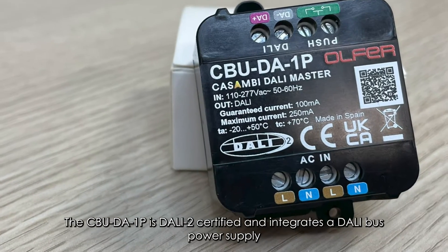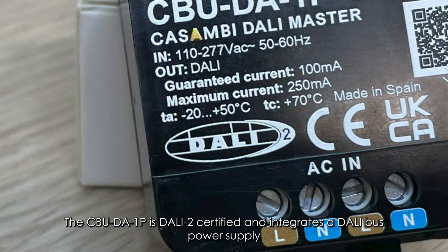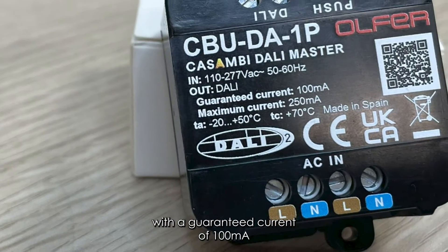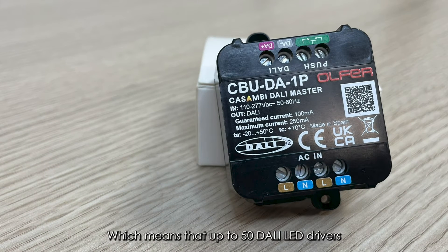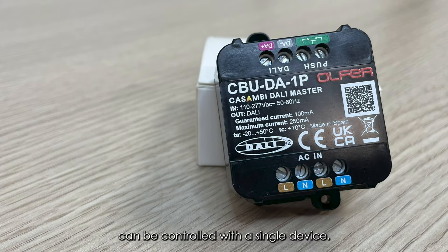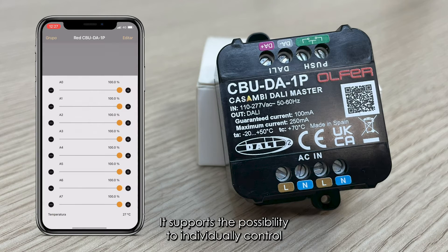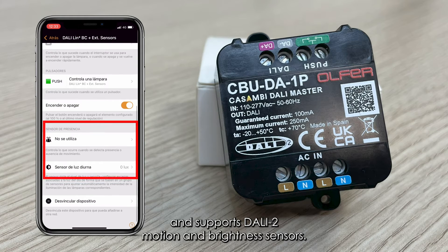The CBU-DA-1P is DALI-2 certified and integrates a DALI bus power supply with a guaranteed current of 100 mA, which means that up to 50 DALI LED drivers can be controlled with a single device. It supports individual control of up to 8 DALI addresses and supports DALI-2 motion and brightness sensors.